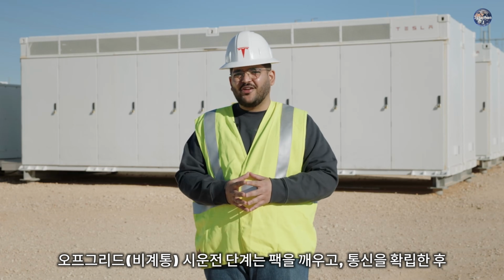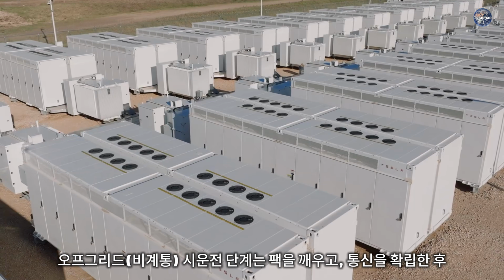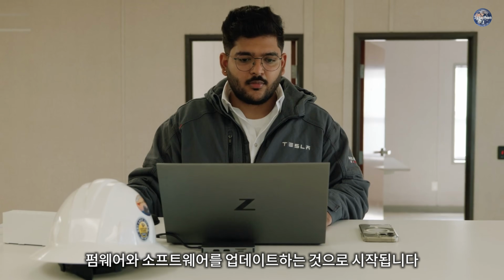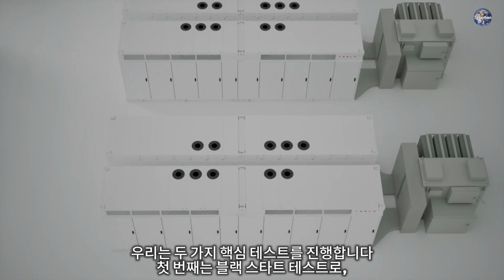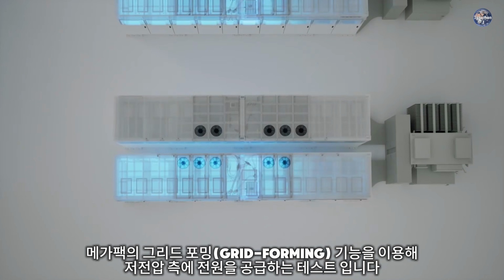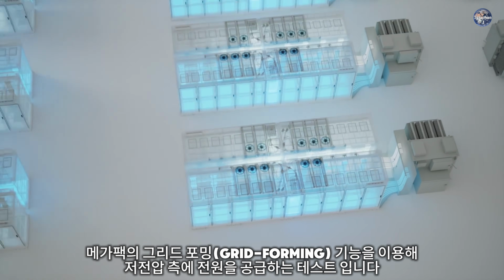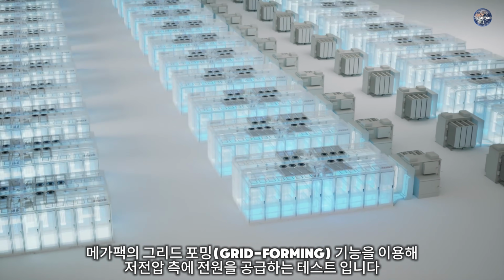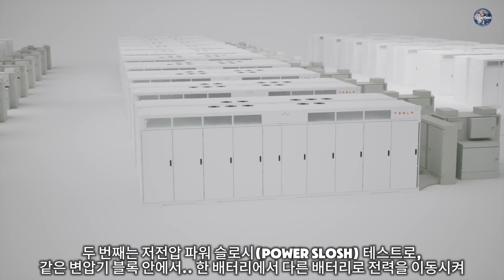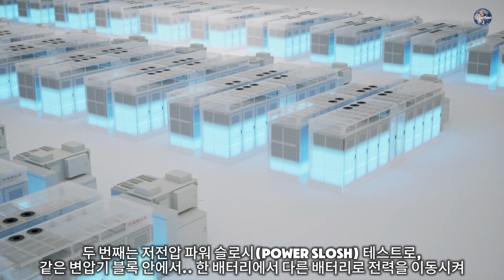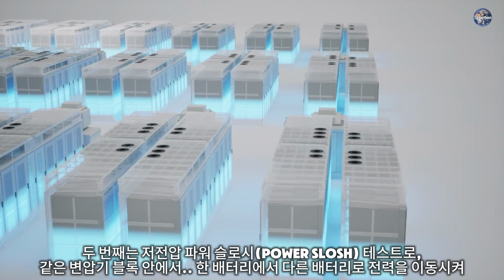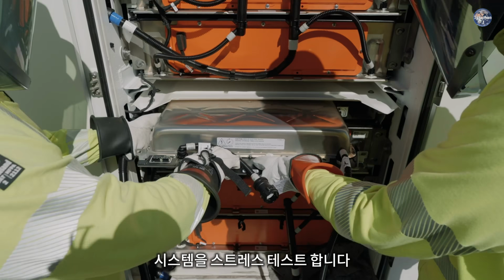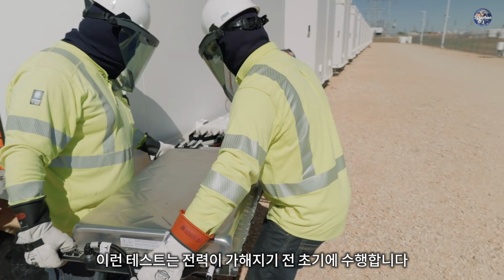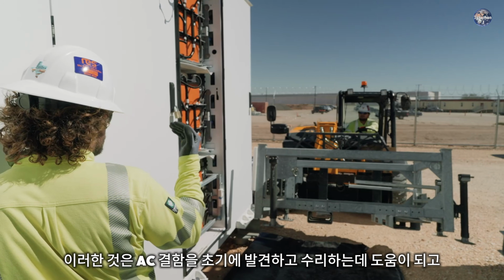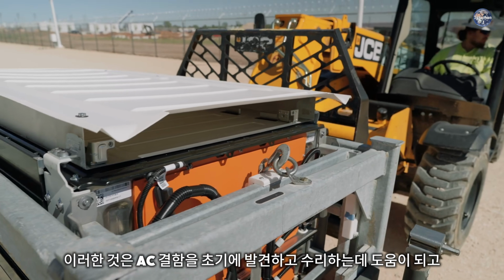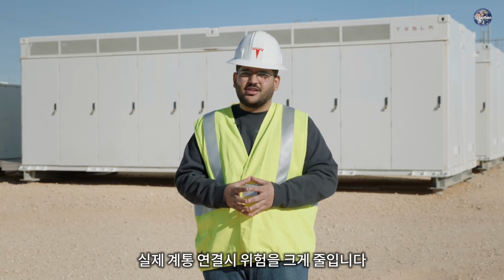The off-grid commissioning phase starts off with waking up the packs, establishing communications, and then updating the firmware and software. The 2 key tests that we run are the black start test, where we power up the low voltage side using the Megapack grid forming capabilities, followed by a low voltage power slosh, which helps us move power from one battery to another on the same transformer block to stress test the system. Doing these tests early in a pre-energized phase helps us spot any AC faults early on and make those repairs. And this considerably de-risks energization as well.